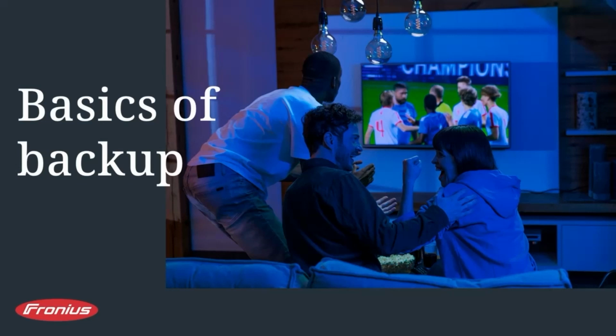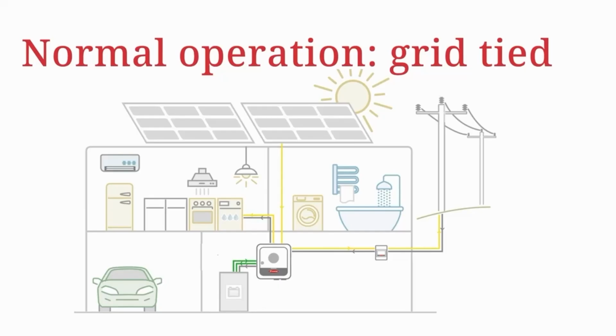So let's have a look at the basics of grid backup systems. Under normal operations, your grid-tied PV system will be able to generate energy from the rooftop, feed that into the inverter, and then distribute that energy to the loads within the property, and potentially export energy that's unrequired locally back to the grid, if there's no limit for that system.